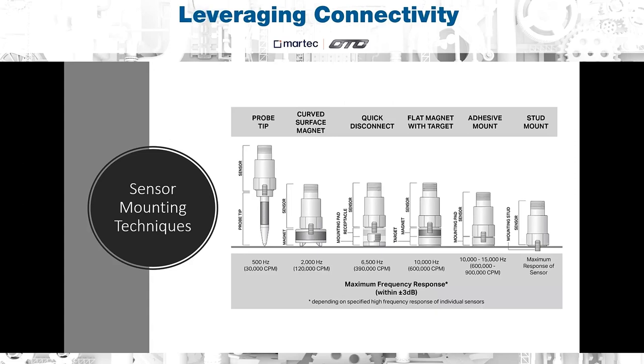Another great way to think about it is many bearing faults or common machine faults will begin at a very high frequency, and then as they get worse and begin to degrade further, the fault frequency, as they call it in vibration analysis, will actually decrease until eventually it's visible by the human eye and you can see the machine shaking itself. We all know at that point, there's not much we can do. So the higher the frequency response of the accelerometer you're using, the more time and the earlier warning you will get of common faults occurring in your machine. So you might see a machine fault that you still might have 6 months of running your bearing before you actually have to correct it. But now you have extra time to plan your shutdown, plan your maintenance, instead of reacting to faults as they occur in real time.